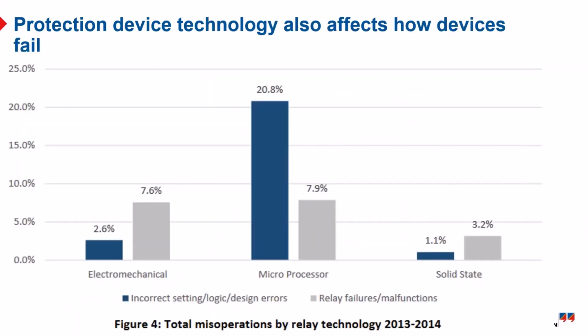Breaking this same report down a little bit further, we can see how the protection device technology affects how these relays actually fail. Here, as you might expect, microprocessor relays have a much higher rate of incorrect setting, logic, and design errors than electromechanical relays. That really shouldn't be any surprise, because the settings on microprocessor relays have steadily grown in complexity over the years, and it's pretty easy to get a forward slash instead of a backslash, or an asterisk instead of a plus somewhere in the logic, and have the thing misoperate.